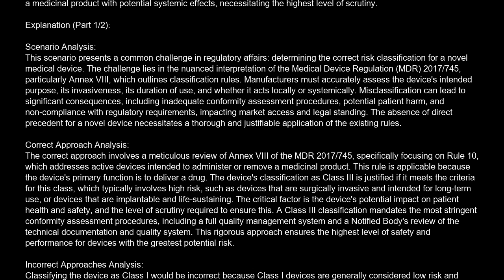Correct approach analysis. The correct approach involves a meticulous review of Annex VIII of the MDR 2017/745, specifically focusing on Rule 10, which addresses active devices intended to administer or remove a medicinal product. This rule is applicable because the device's primary function is to deliver a drug. The device's classification as Class III is justified if it meets the criteria for this class, which typically involves high risk, such as devices that are surgically invasive and intended for long-term use, or devices that are implantable and life-sustaining. The critical factor is the device's potential impact on patient health and safety, and the level of scrutiny required to ensure this. A Class III classification mandates the most stringent conformity assessment procedures, including a full quality management system and a notified body's review of the technical documentation and quality system. This rigorous approach ensures the highest level of safety and performance for devices with the greatest potential risk.